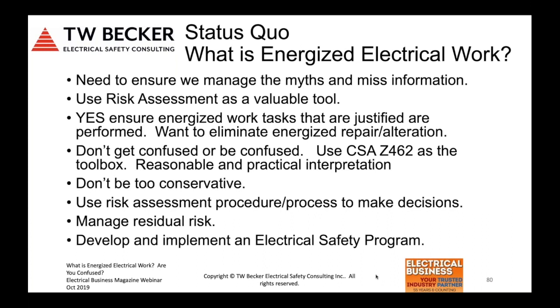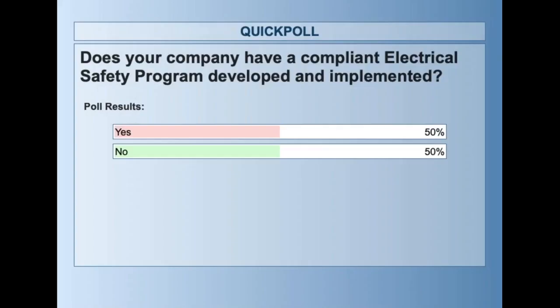Manage the residual risk determined by ensuring that the hierarchy of risk control methods is applied by the worker. And all of this is facilitated by developing and implementing an electrical safety program. Based on the poll, we almost had a 50-50 response that compliant programs are in place. My opinion is I think it's far less than 50% of industry in Canada or the US that has a compliant electrical safety program. It actually was 50-50. Thanks, Anthony, for bringing that poll back up.